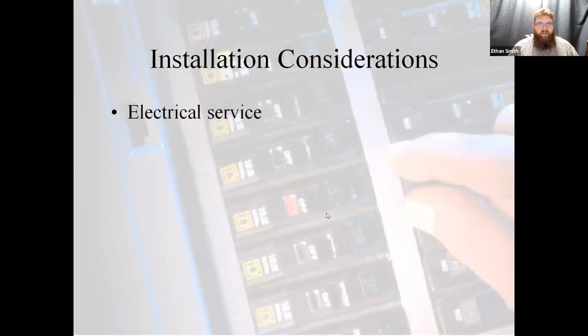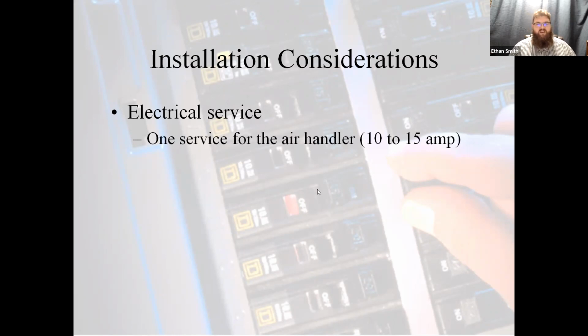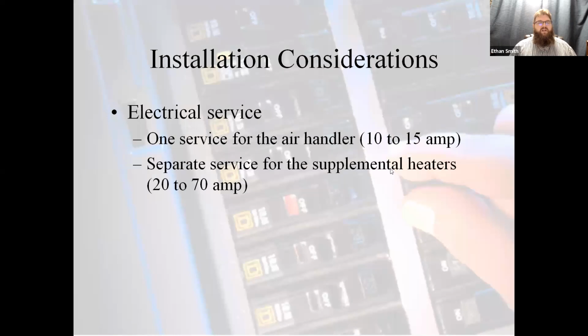Okay. Other things to consider is your electrical service. Your heat pump is going to have a higher electrical requirement than your equivalent air conditioner. That's because we've got extra controls. We generally have a sump heater in the outdoor unit, and make sure that your electrical service is up to snuff. On indoor units, if you're running electric heat, you need to make sure that you have electrical service that will satisfy both the air handler requirement and the electric heat requirement. Very frequently, this requires separate electrical services for the air handler and the electric heat. So make sure you've got all that there as the need may be. Typically, the air handler requirements are going to be pretty low, 10 to 15 amps, and supplemental heaters may range from 20 to 70 amps.